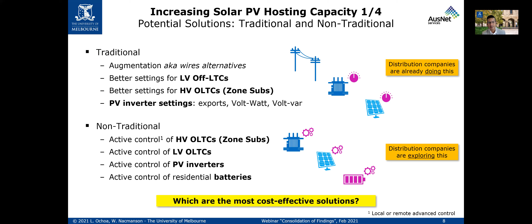For instance, just increasing the wires, conductors, or transformers might solve the ampacity problems—meaning you can handle larger currents and reverse power flows—but not necessarily the voltage problems, depending on how the impedances change. Managing off-load or on-load tap changers will definitely help with voltages, but won't help with asset congestion issues. Same thing with the PV inverter settings—our standards are mostly there to help manage voltages, but not necessarily the aggregated currents we'll see once many neighborhoods are exporting power.